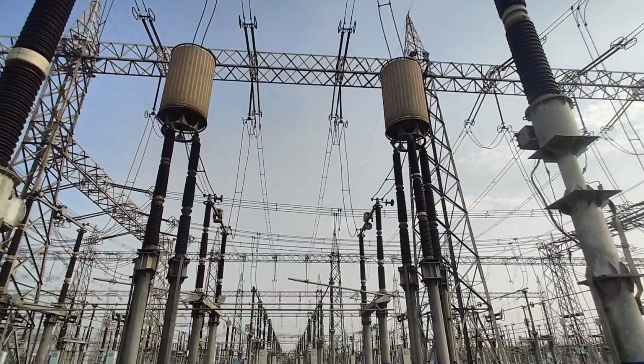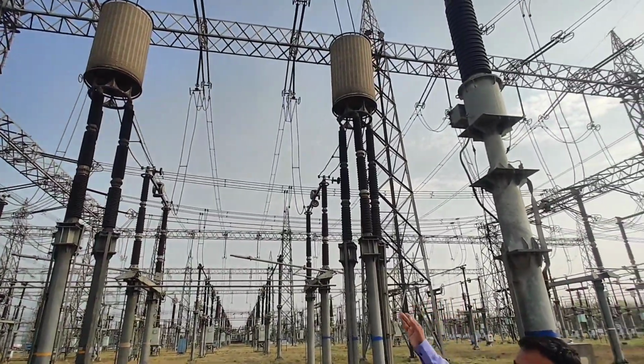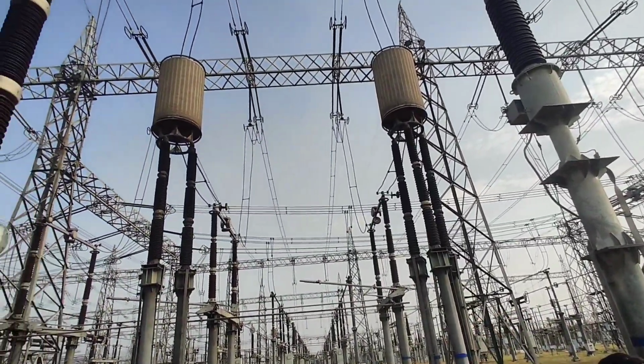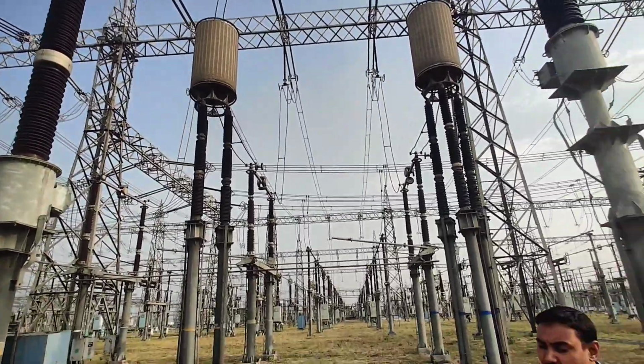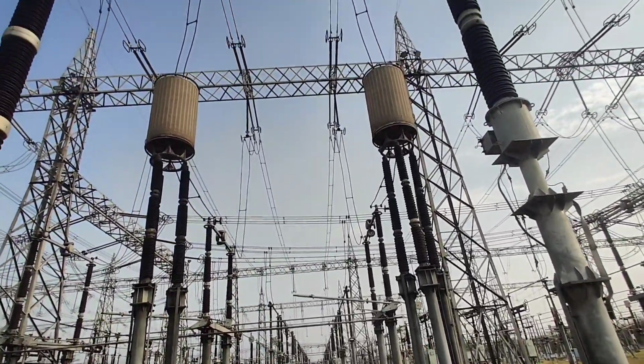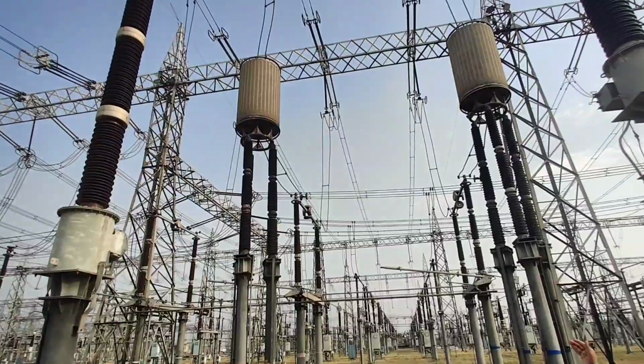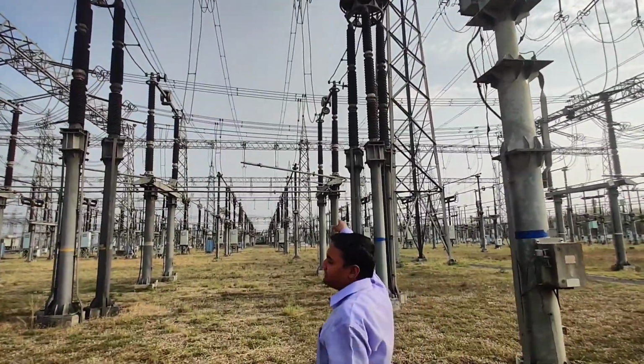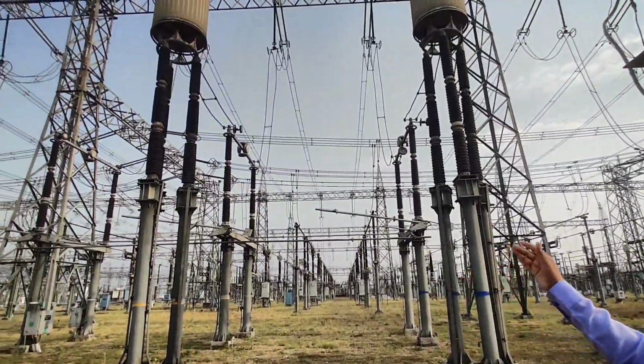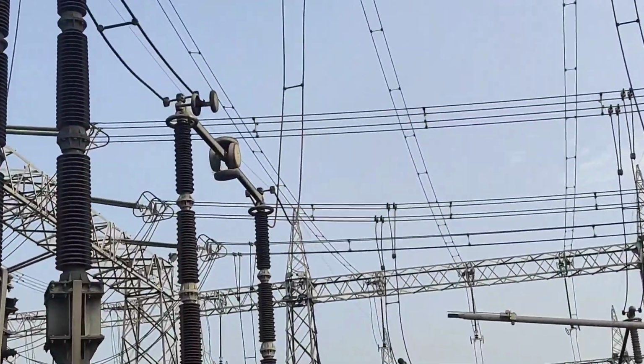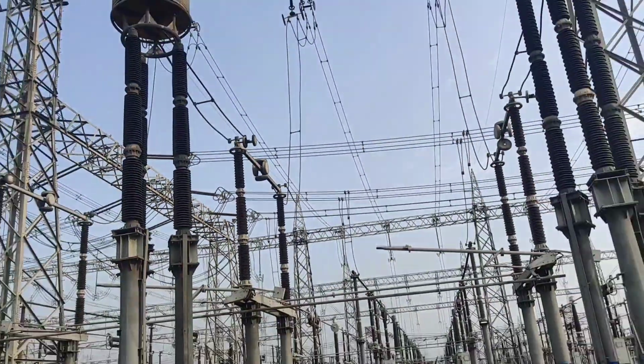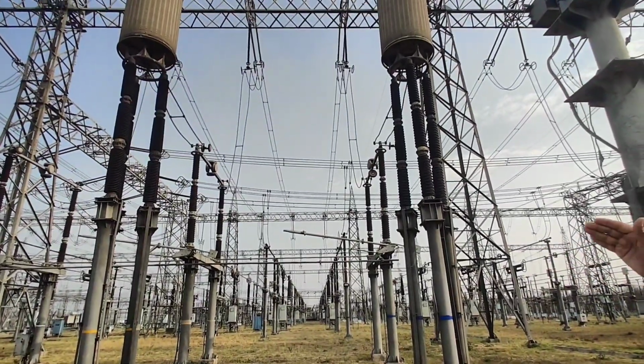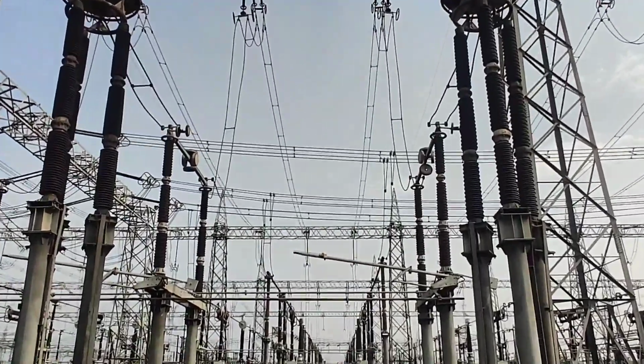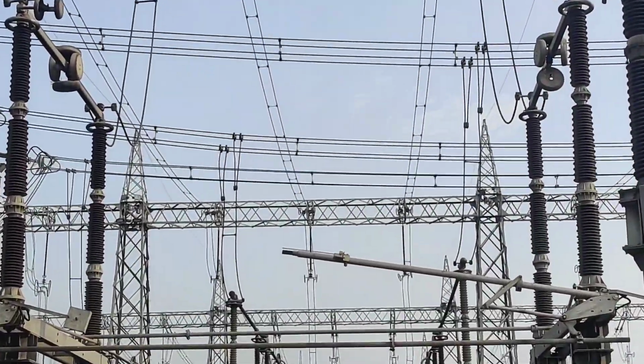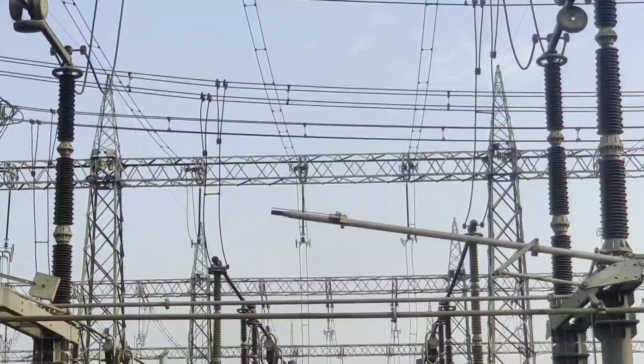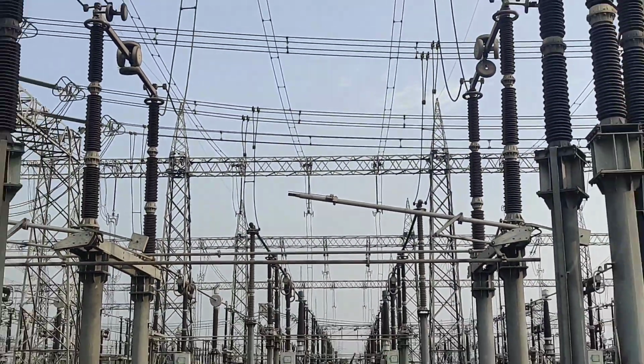And if you see here, the wave traps are generally installed only in 2 out of the 3 phases. We will see again why this is only on 2 phases and not on 3 phases. After this wave trap, the next element that comes is your isolator, that is the line side isolator, or it is called the line isolator. From the line isolator, the jumper starts, and now it goes to the switchyard end where it is connected to the bay equipments or the main bay equipments.